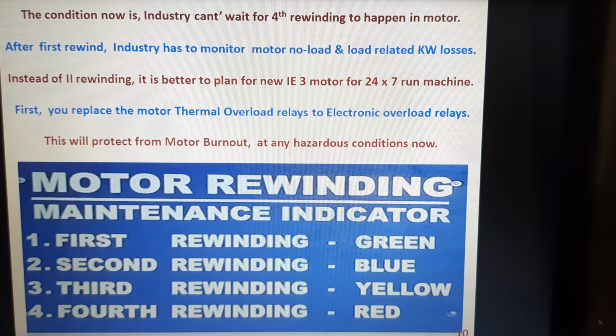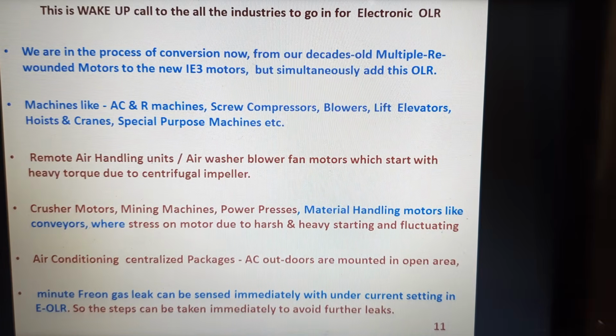First, replace your motor's thermal overload relay with an electronic overload relay, and this will protect the motor from further burnouts in case of any hazardous conditions from now on. This is a wake-up call to all the industries to go for an electronic OLR. It can be a motor protection relay or a pump protection relay. We are in the process of conversion from our decades-old multiple rewound motors to new IE3 motors, but simultaneously plan to add an electronic OLR instead of a thermal OLR.